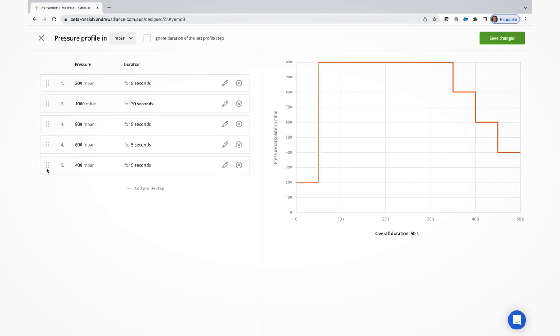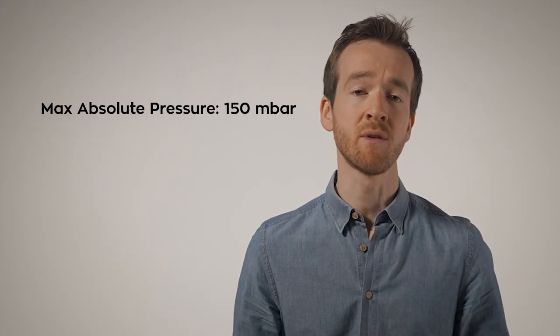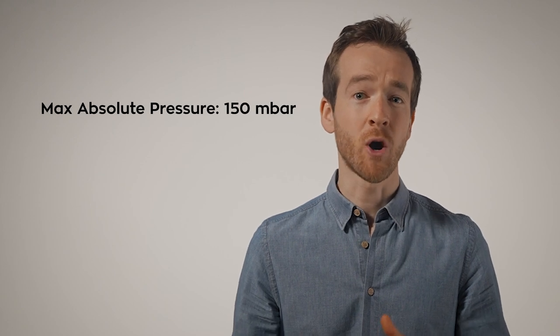The pump can reach an absolute pressure equal to 150 millibars and is equipped with hardware that updates actual pressure status in OneLab as your protocol gets executed, so that you can keep an eye on your protocol status in real time through OneLab, even if you're not in the lab.